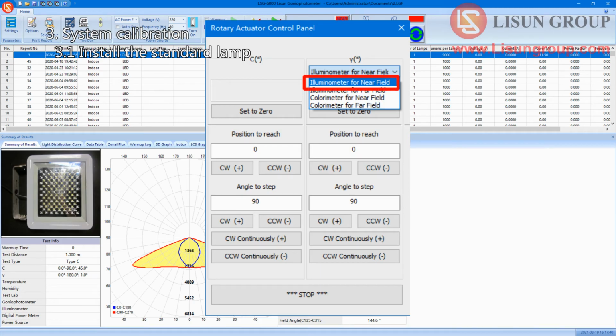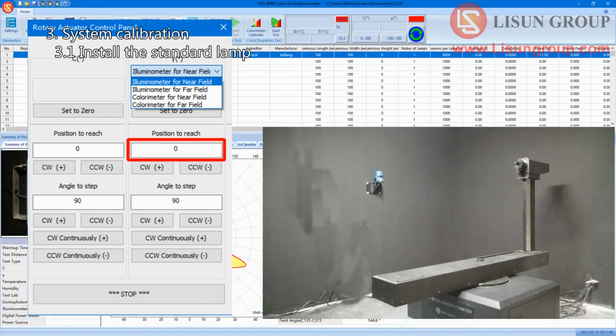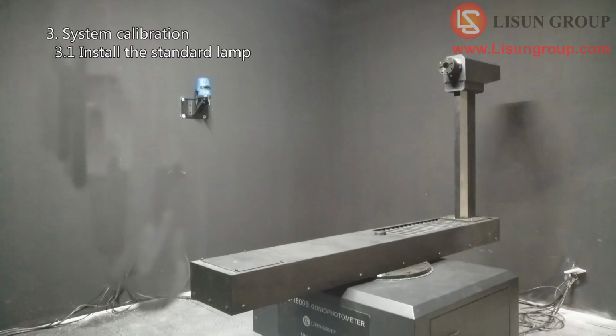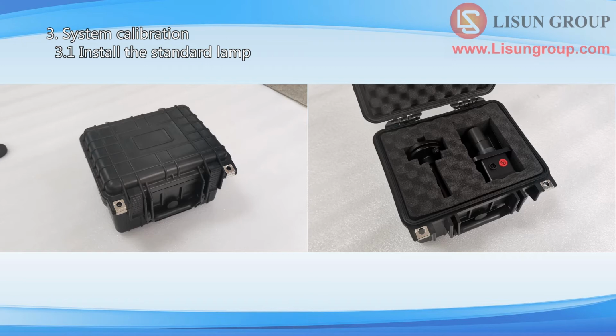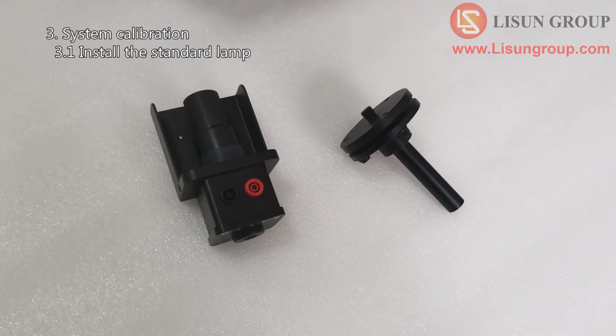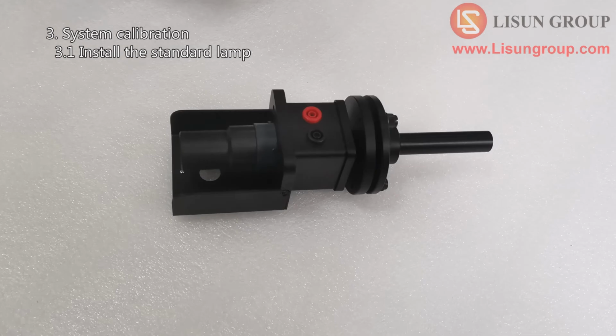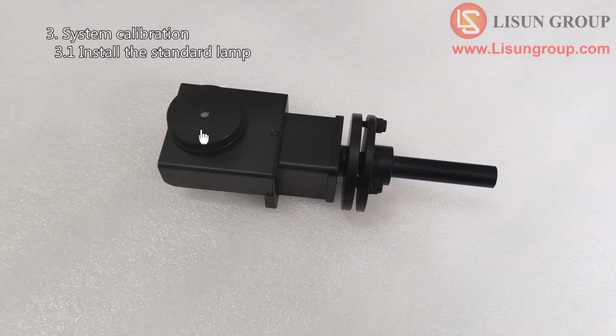Choose Illuminometer for near field. Rotate the gamma angle to 0 degree position. Turn on the cross laser and make sure that the laser hit the correct direction. Take out the standard lamp. Assemble it as shown in the figure. Also install the mirror tool.